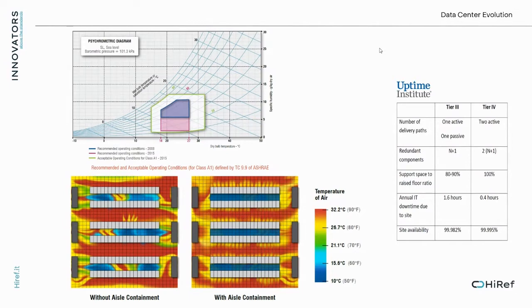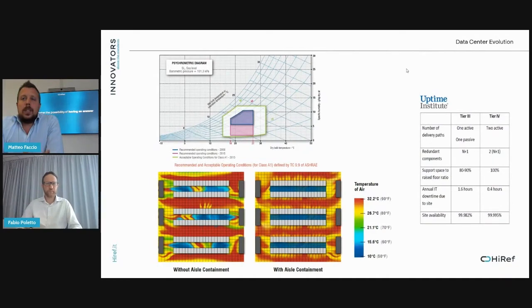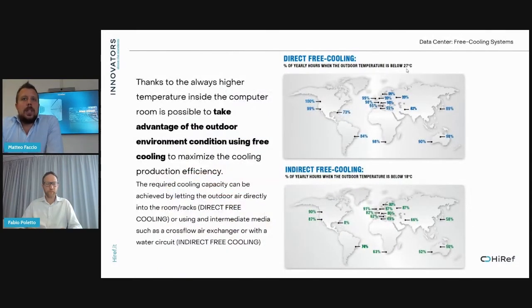Last but not least, we can also use the exceeding number of units normally used for redundancy. For example, for tier 3 or tier 4, we have N+1 or 2N configurations. We can use these exceeding units and make them run too, finding a balance with a better efficiency working point. But the key point is the temperature. The temperature inside the white space has been increasing, reaching up to the limit, and this gives the possibility to take advantage of the outdoor environment using free cooling.